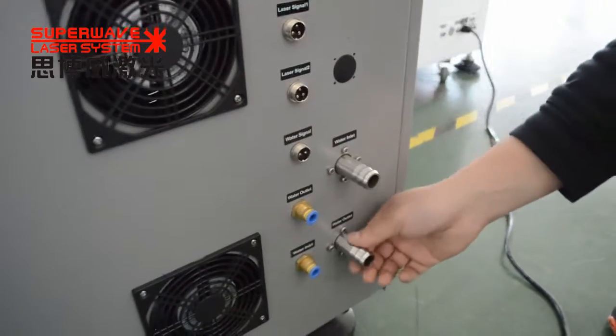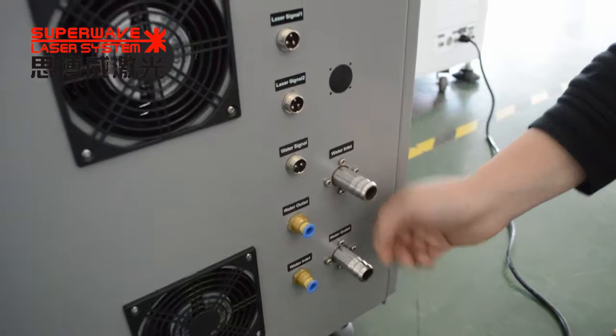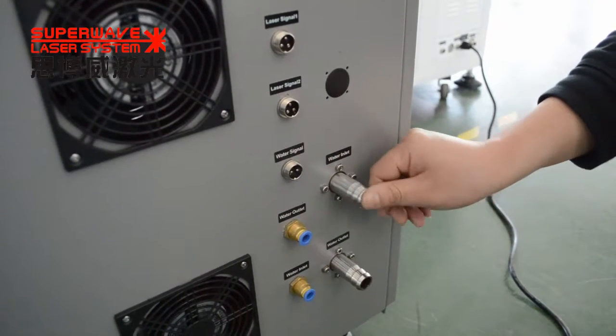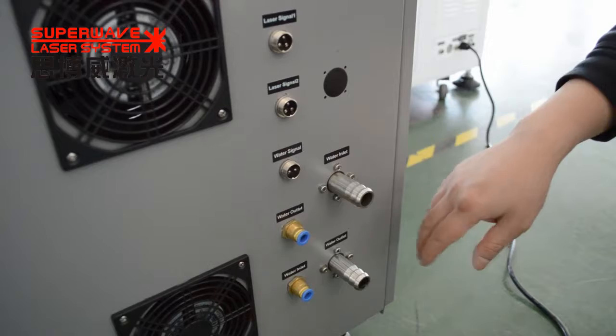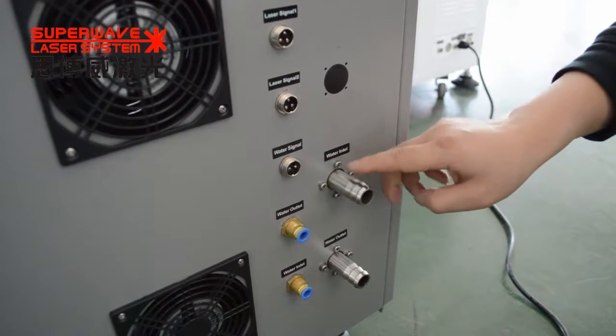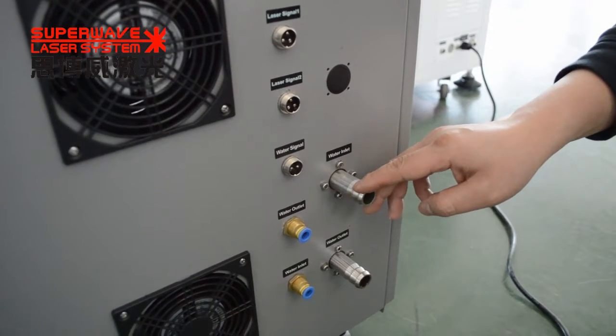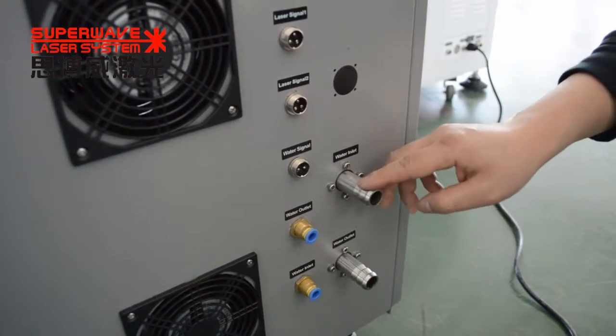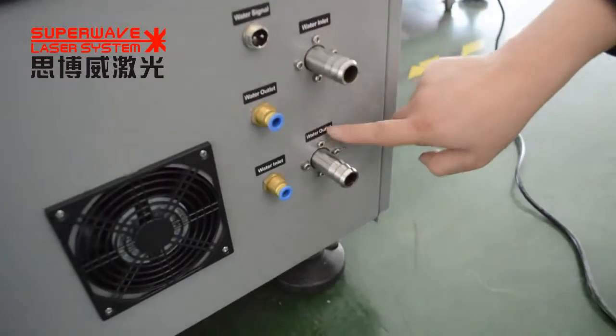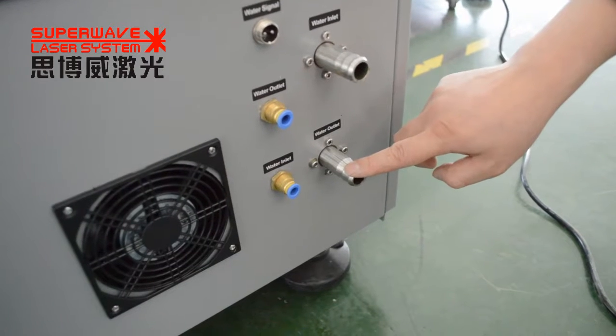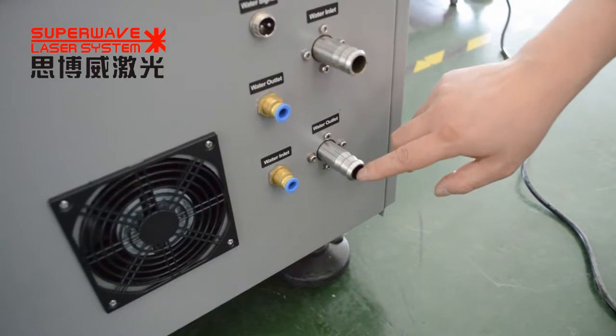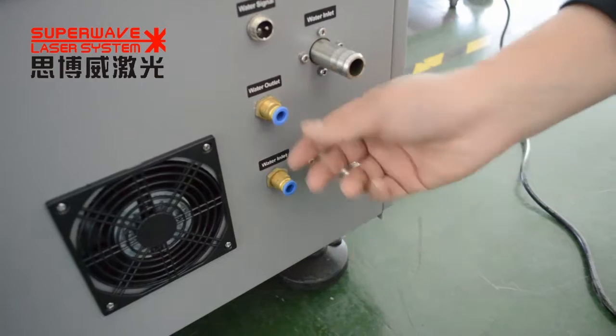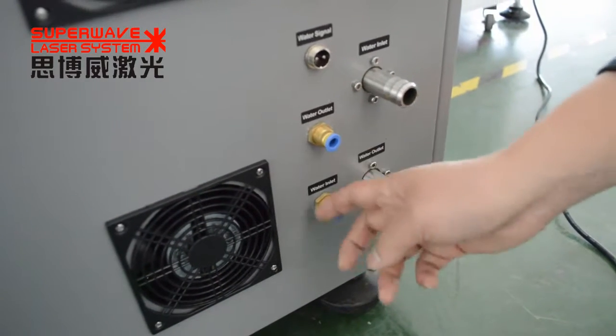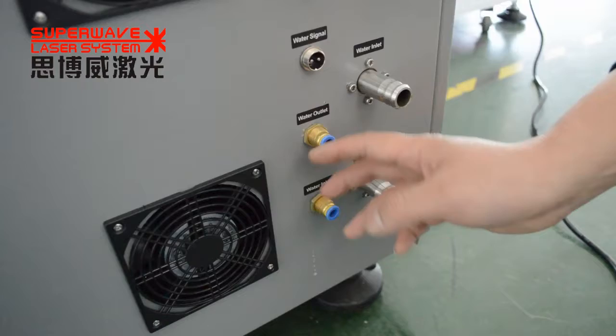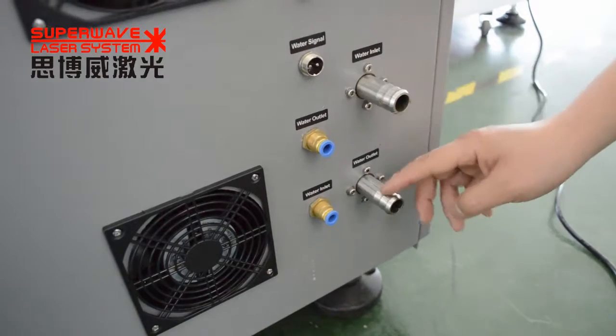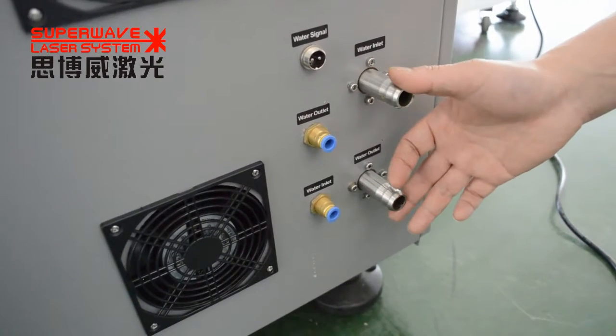This must connect to the chiller for cooling the laser head. This water inlet connects to the outlet from the chiller. Water outlet connects to the water inlet from the chiller side. This water tube has no direction, but this one has direction. Don't make a mistake.